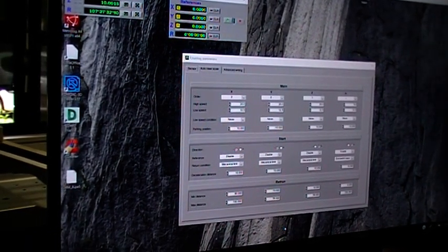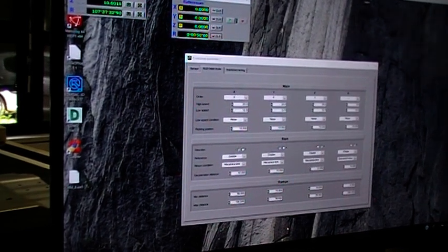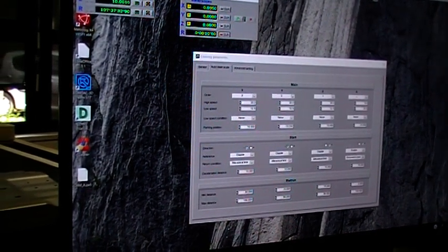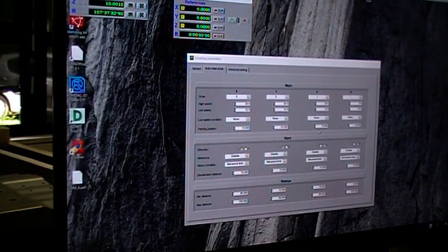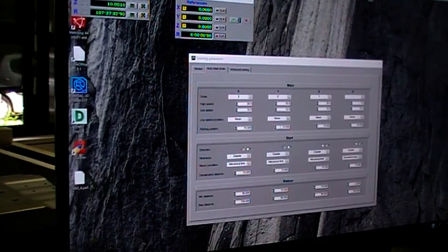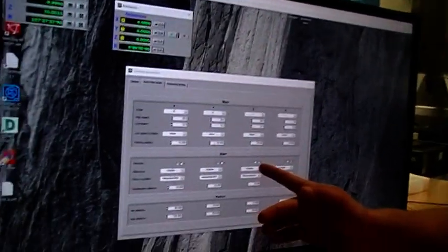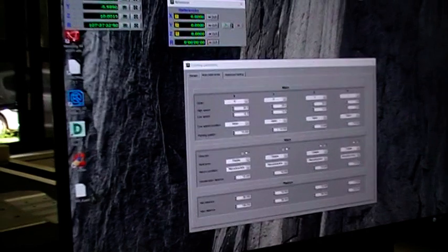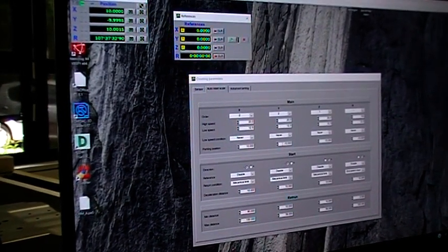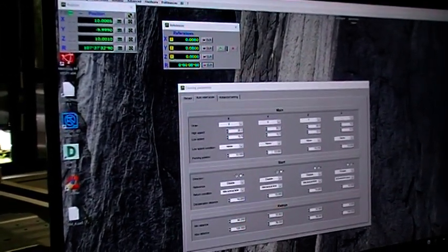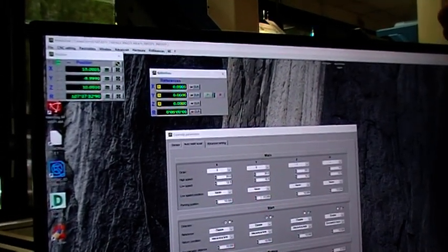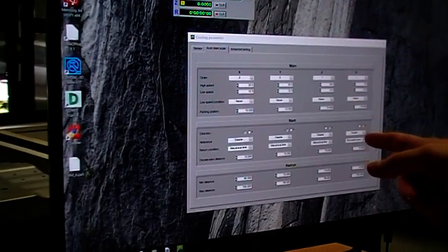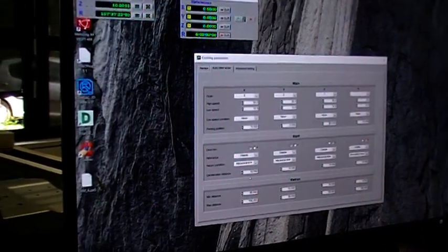Okay. Then there is a really small problem, that is the parking position for Z and for Y. So if you say you start up, then return condition, then go down. So it will take 10 up, see the reference mark and you stop 10 mm after. So this value is not 10, it's minus 10. And this one, on the other hand, is plus.